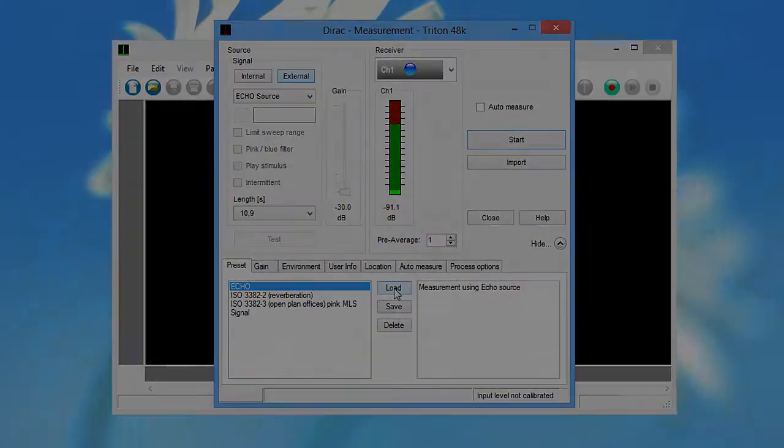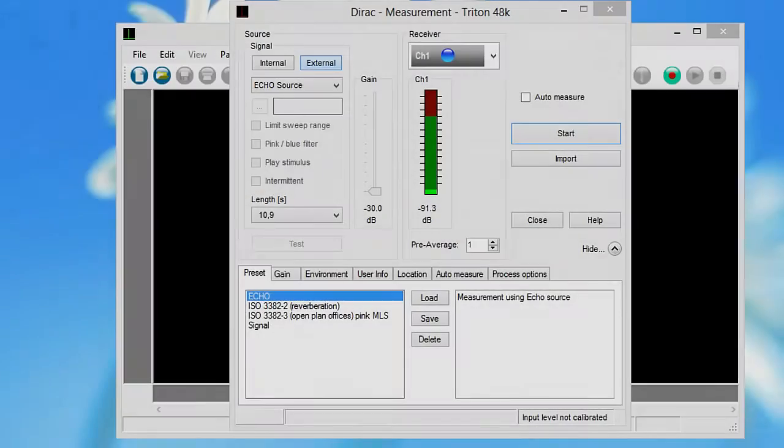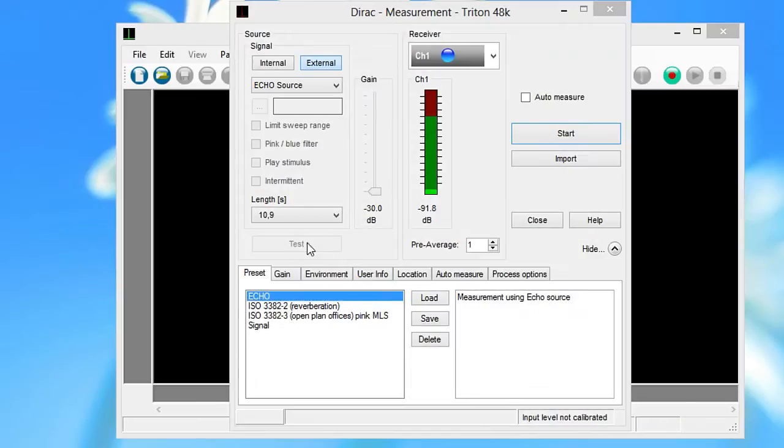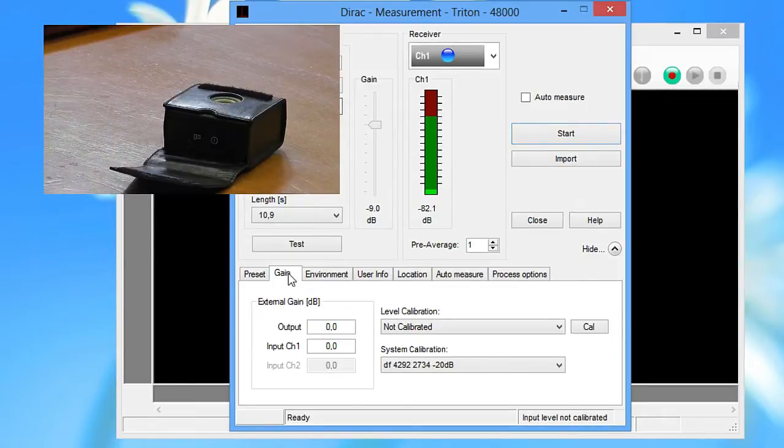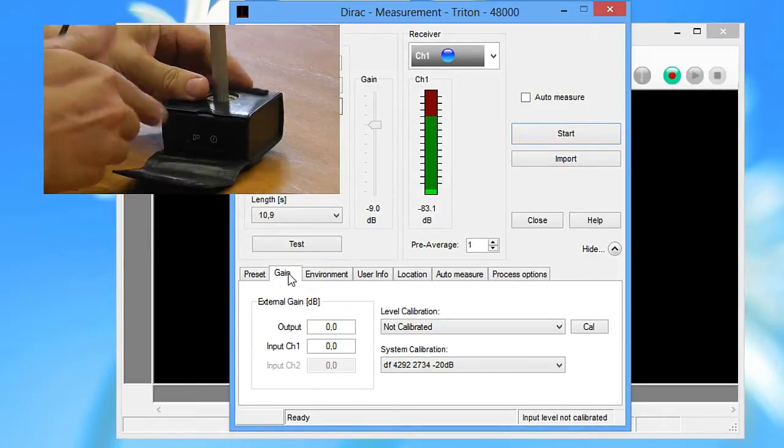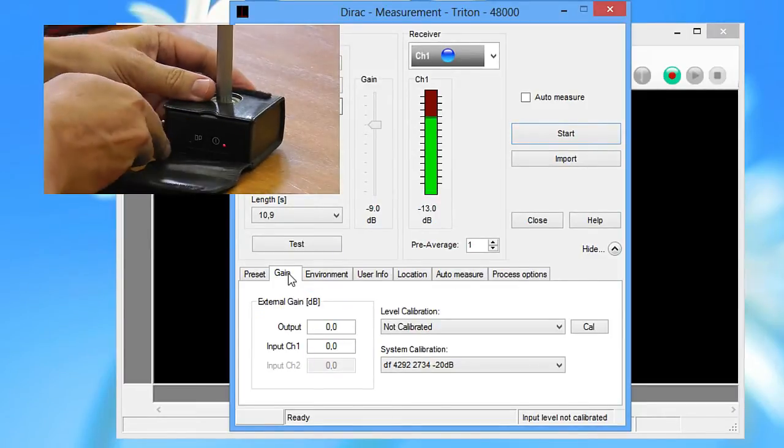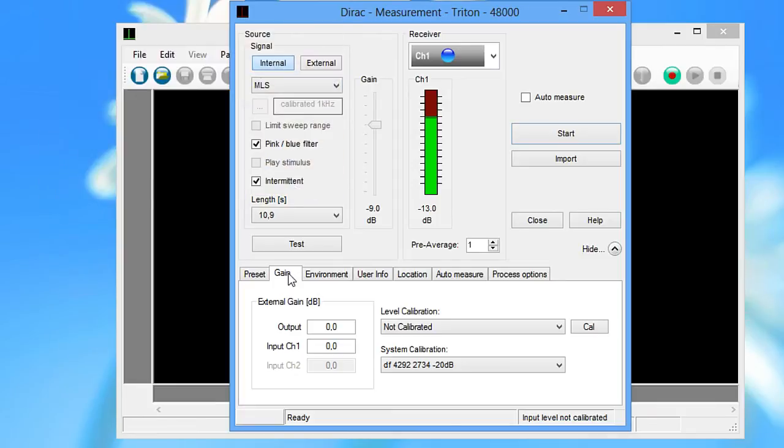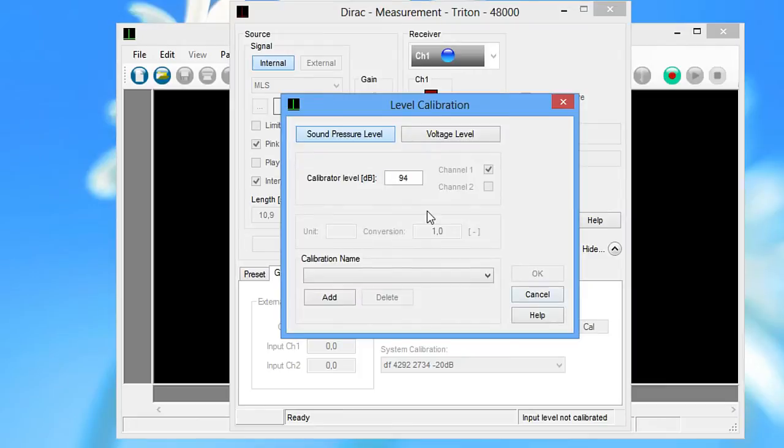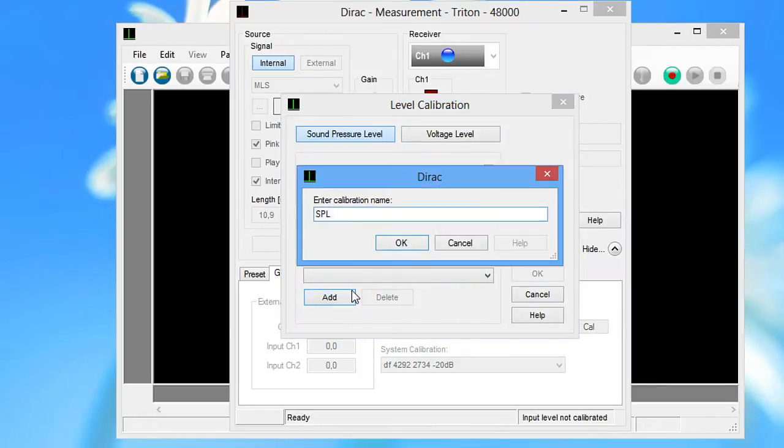However, before you can do a measurement, you need to perform a level calibration. To do so, insert the microphone into the calibrator and start the calibration on the gain tab. Enter the calibrator gain here and use the default name for the new level calibration.